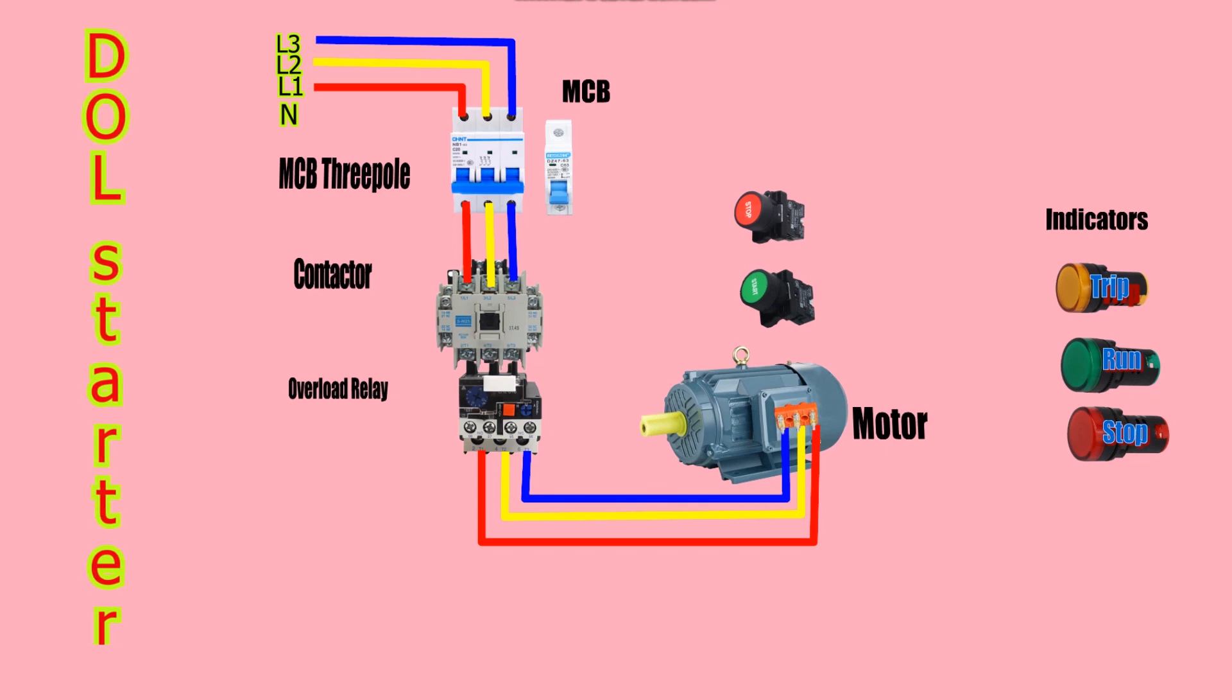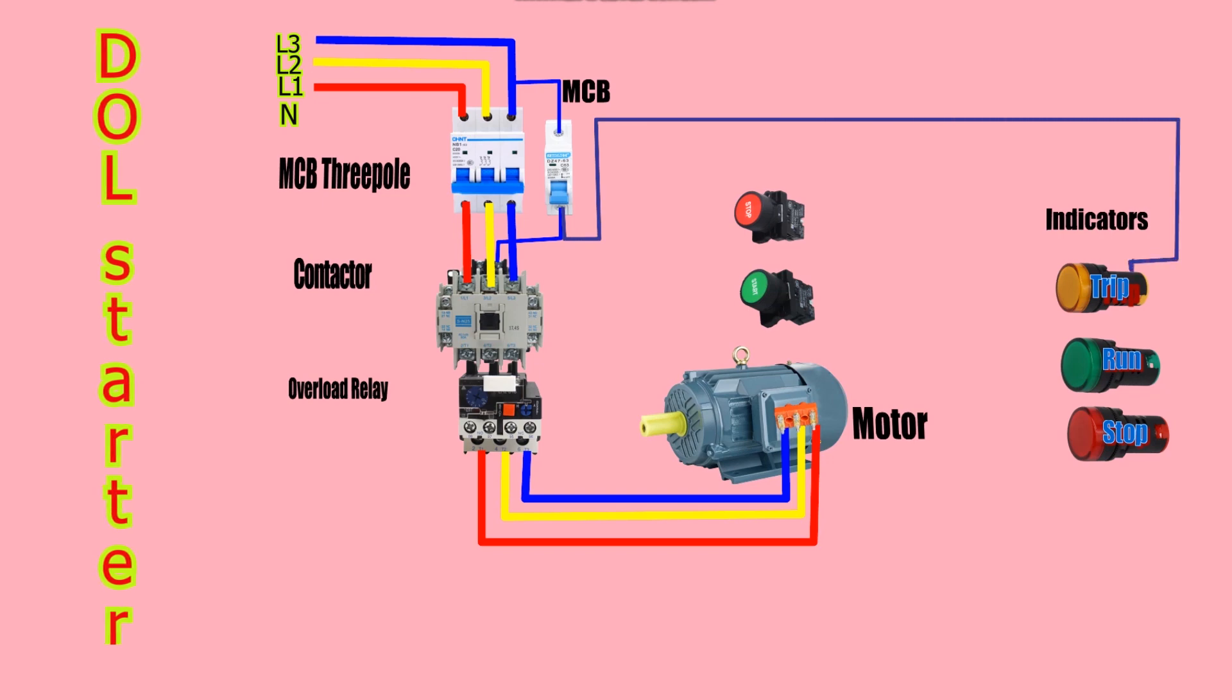To control the motor, a phase is taken from the incoming phases and given to a two-amp MCB. In the diagram provided, the blue phase is used. The output of this MCB is connected to the contactor coil A2 terminal. Another wire is taken and linked to the trip indicator lamp on one side, while looping the run and stop indicator lamps on one side with a wire.